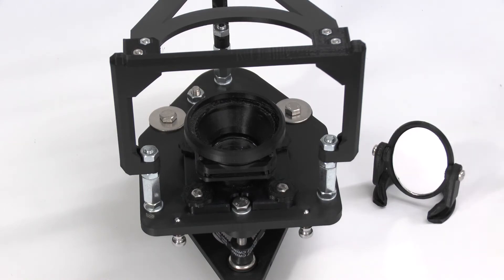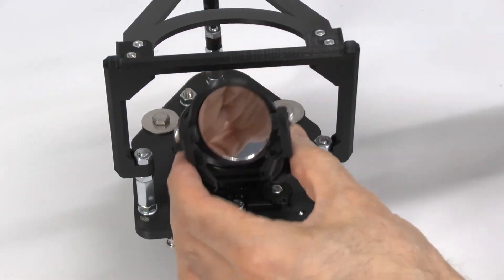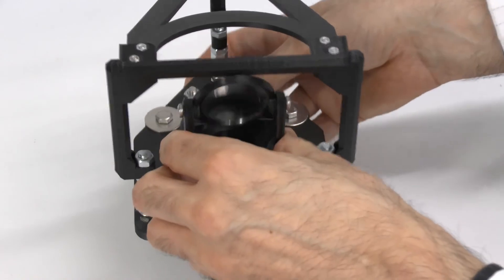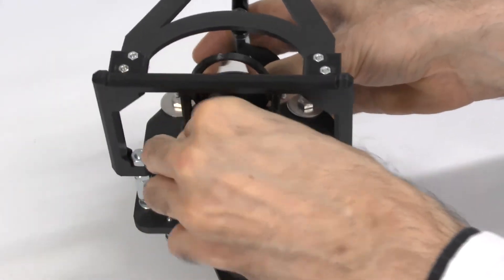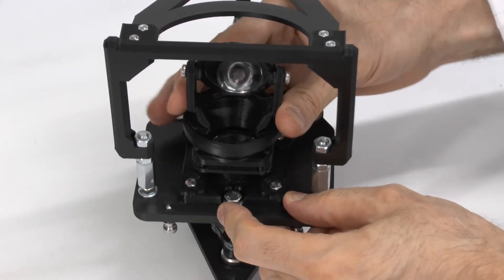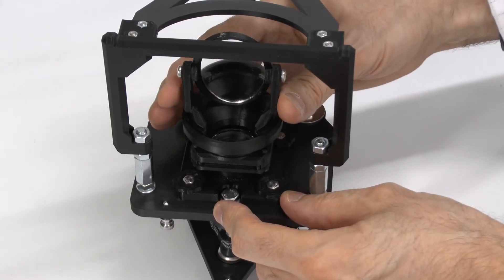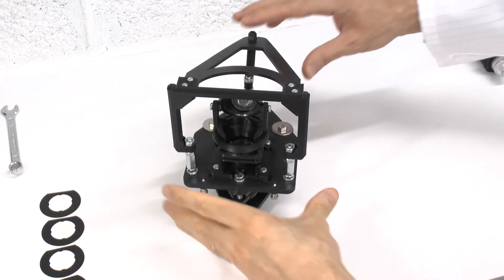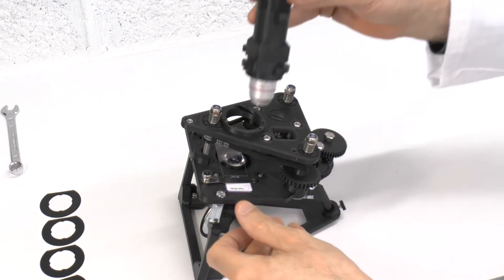You can now fit the mirror-suspend system into the mirror holder socket by squeezing the free ends together and sliding it in at an angle. Now you can put the microscope the right way up, re-attach the optical tube and the upgrade is complete.